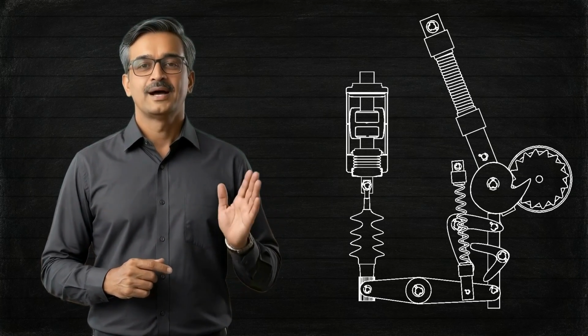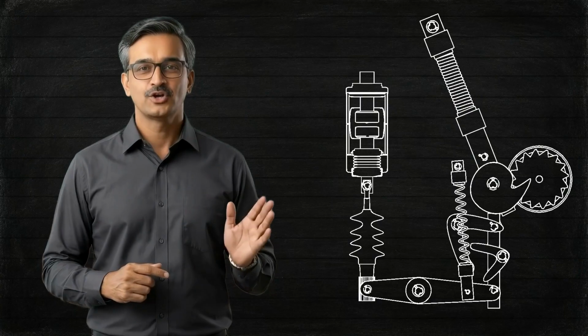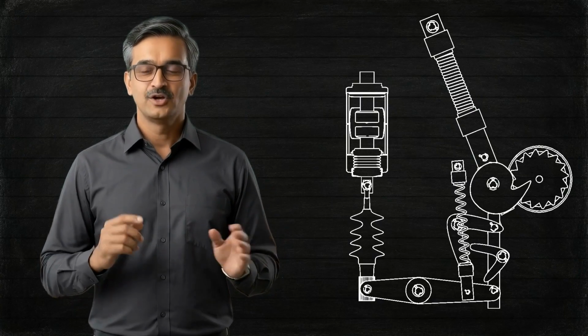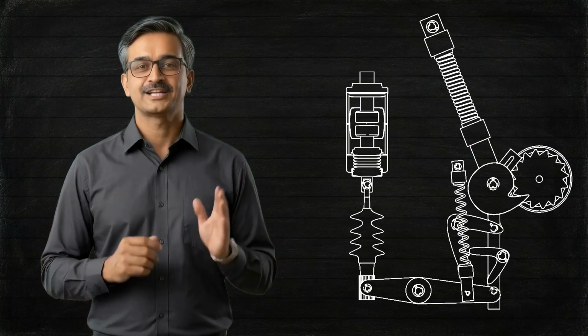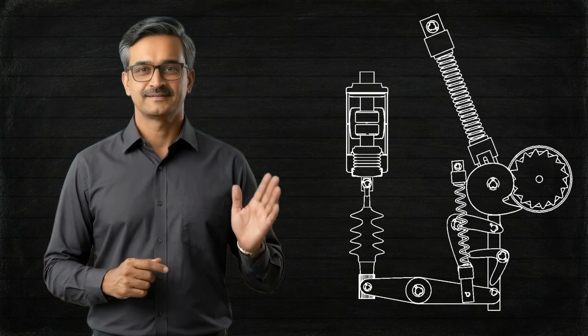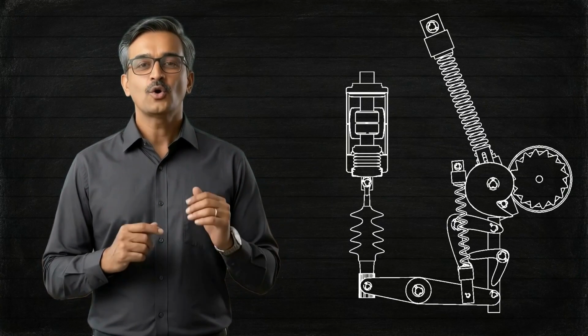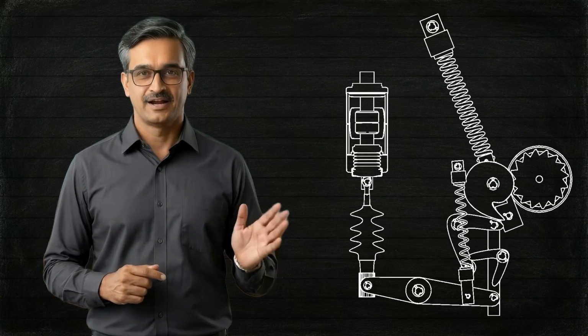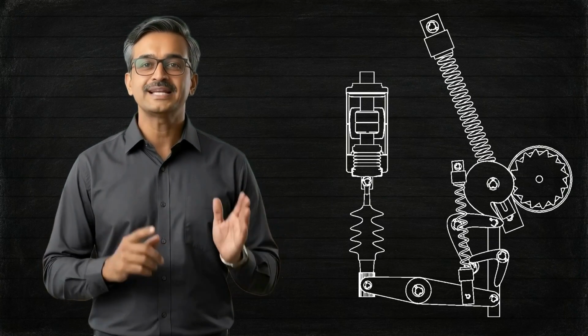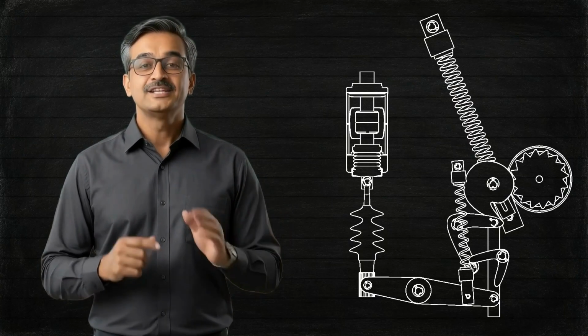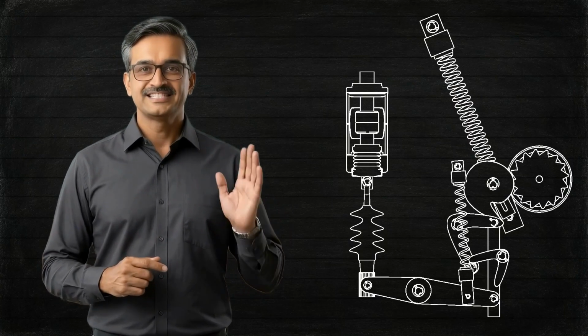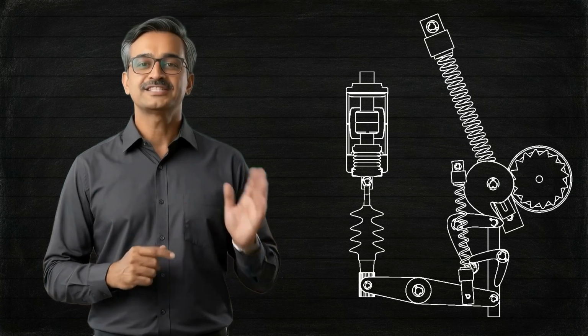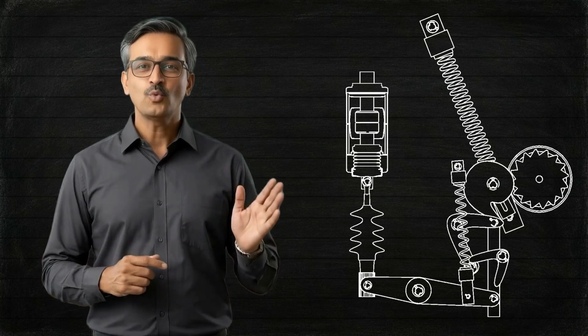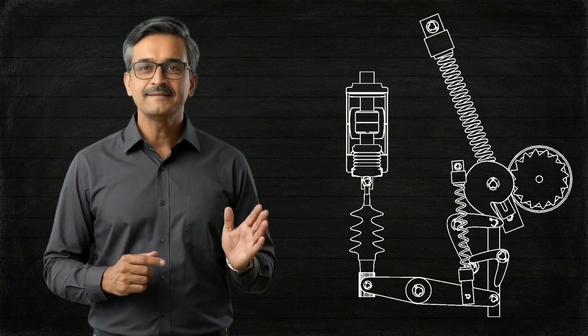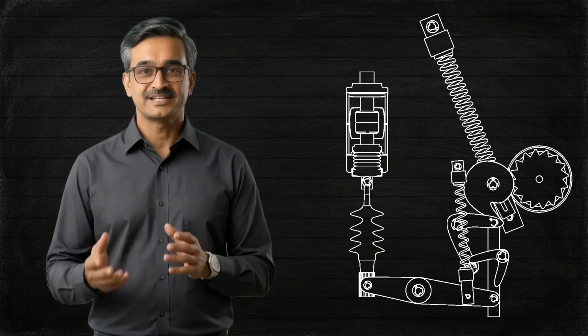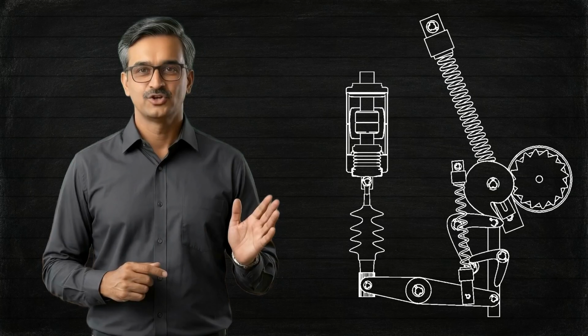Now suppose a closing command is given. Immediately, the closing coil becomes energized. The closing coil simply releases the closing latch. Notice something very important. The closing coil itself does not close the breaker. The coil only unlocks the mechanism. The actual work is done by the stored energy of the compressed closing spring. The spring expands rapidly. Its stored energy is transmitted through the operating linkage. The moving contact travels at high speed. Finally, the breaker closes.